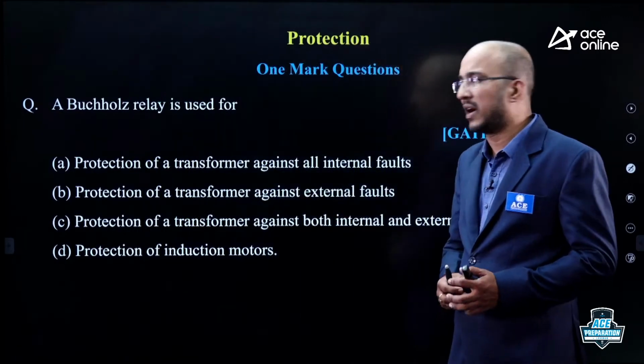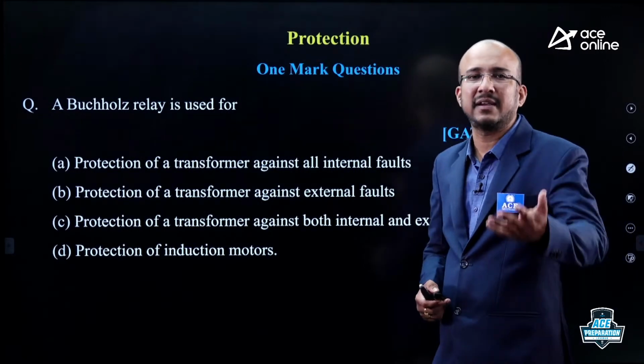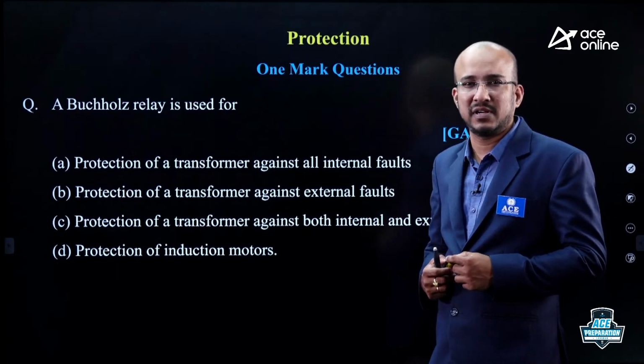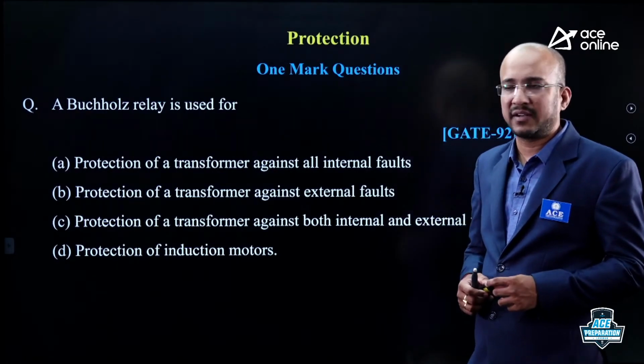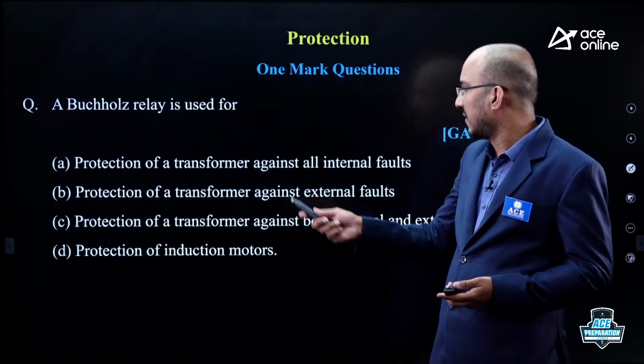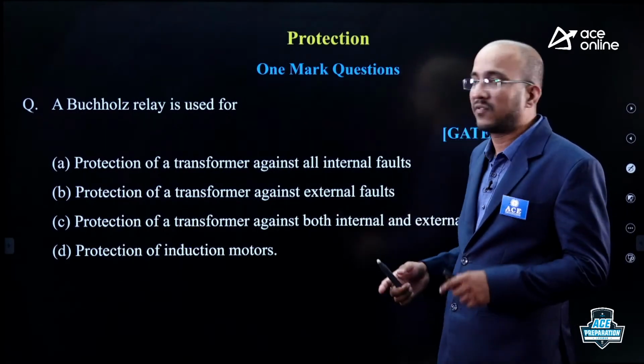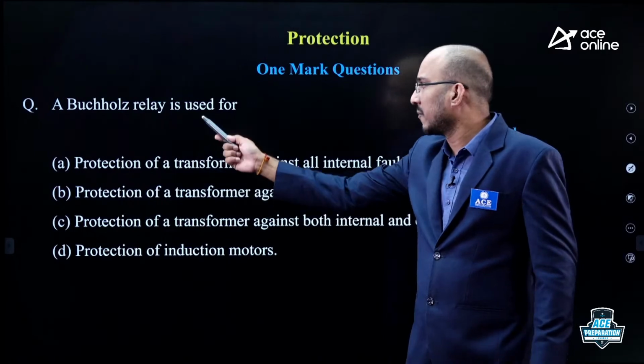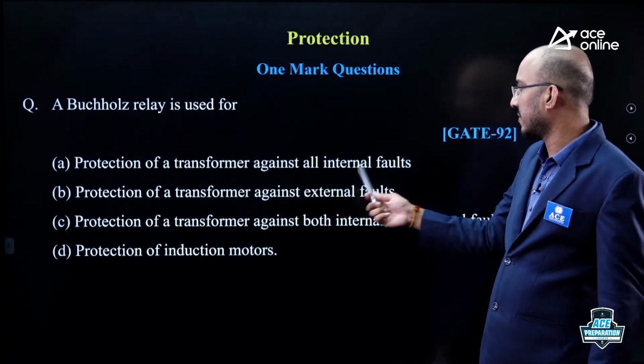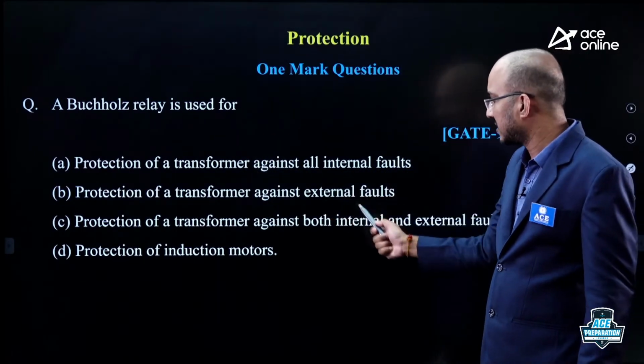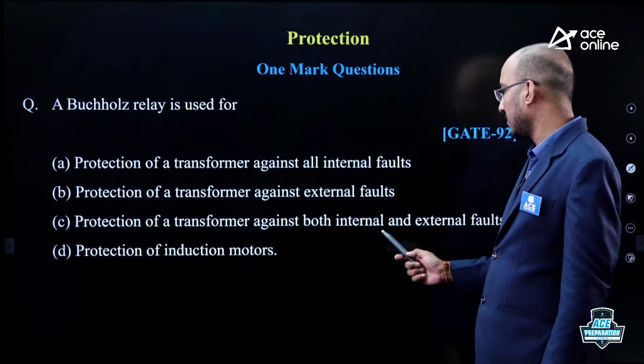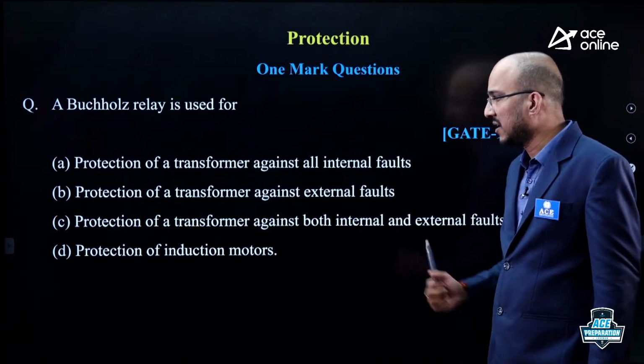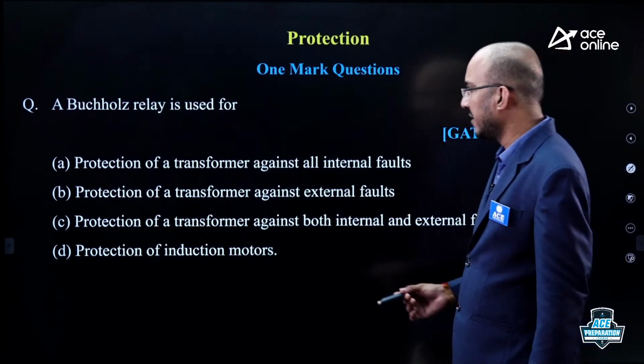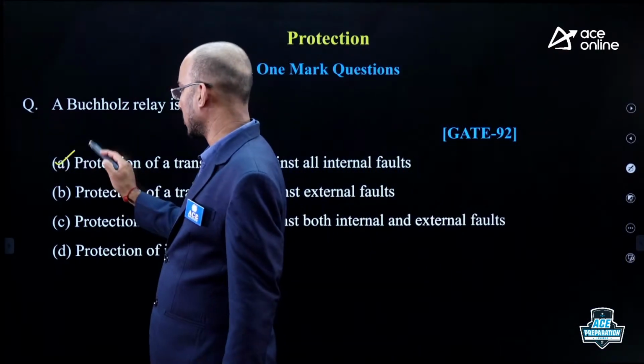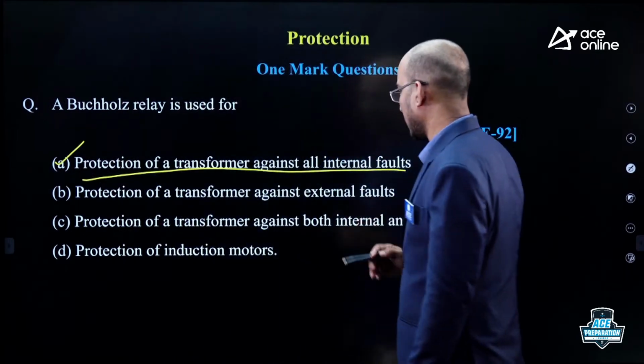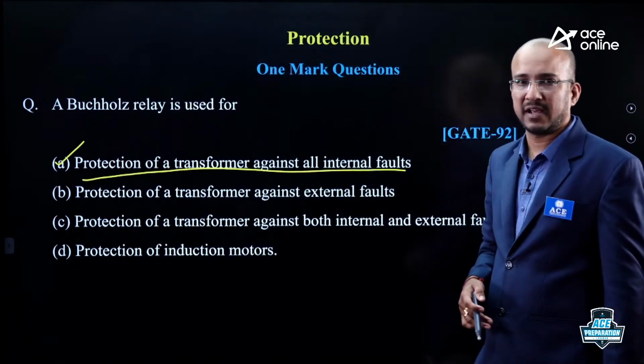Buchholz relay is used for, where do you use the Buchholz relay? In transformer protection. In class we will discuss now. Buchholz relay is used in transformer protection for internal faults or external faults? For internal faults only. So, Buchholz relay is used for protection of transformer against internal faults. Option B, external faults. Option C is both internal and external, and protection of induction motor. Okay. So, which one is the right one? Buchholz relay is used for protection of transformer against internal faults.